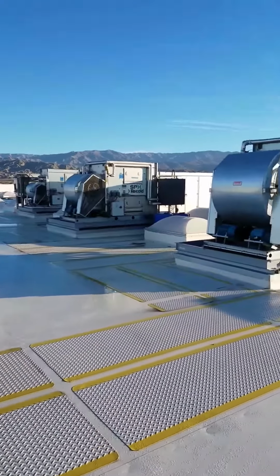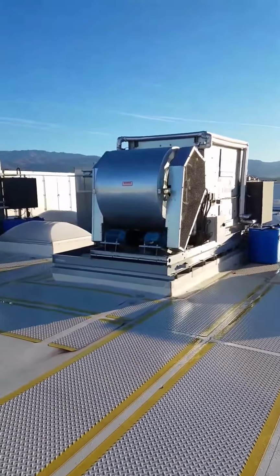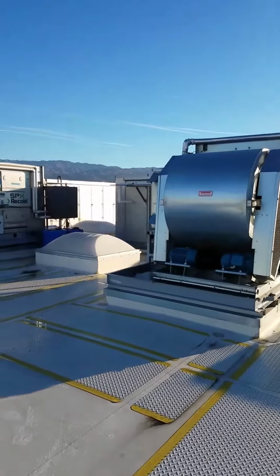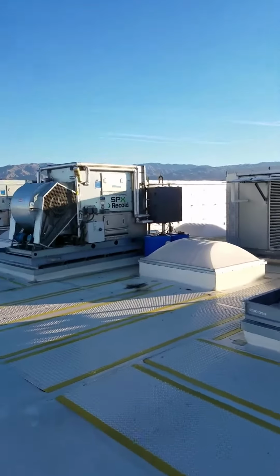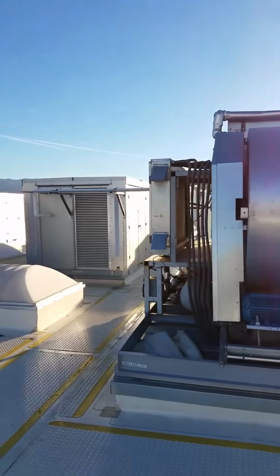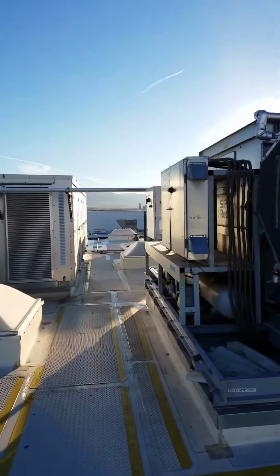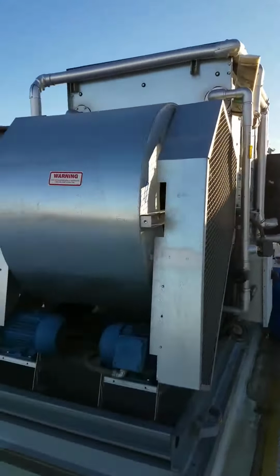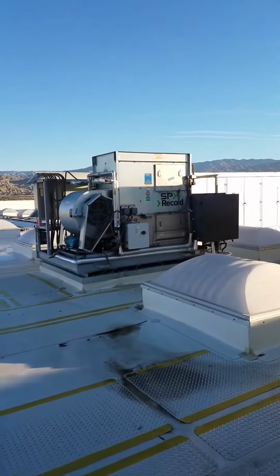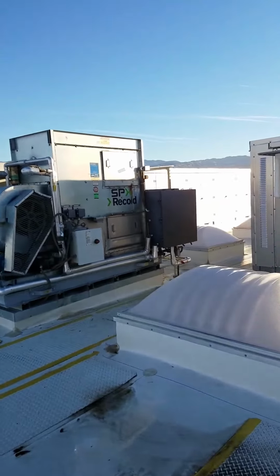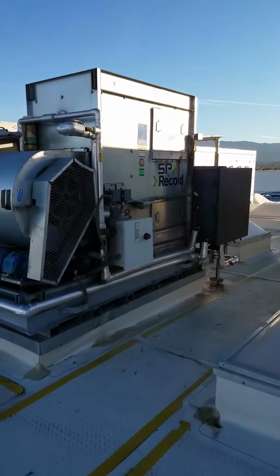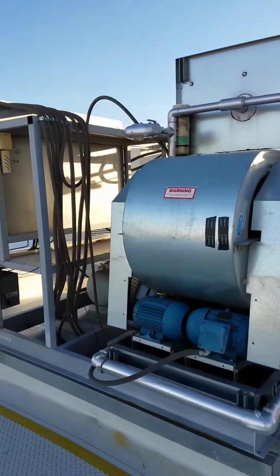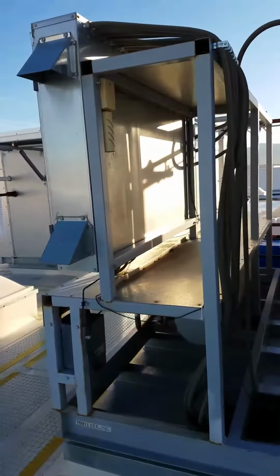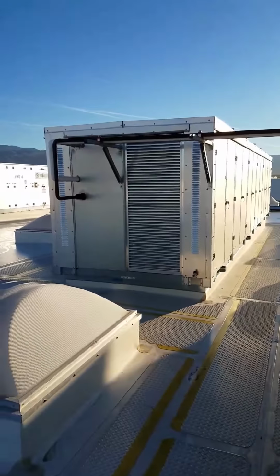Over here at the store, got a call for pump down. These are glycol racks. And then up front we got a CO2 rack. It identified as rack A, pump down. Let's see what's going on.